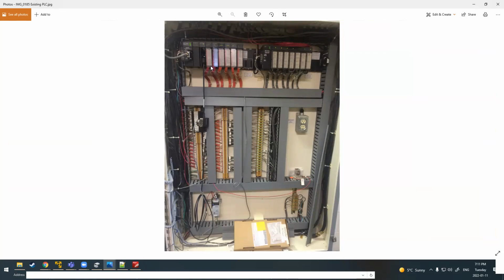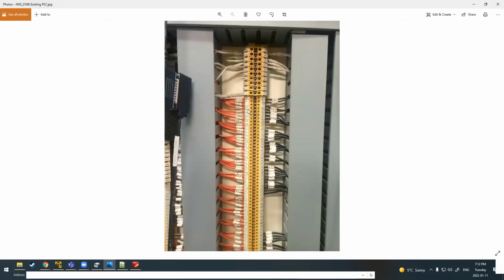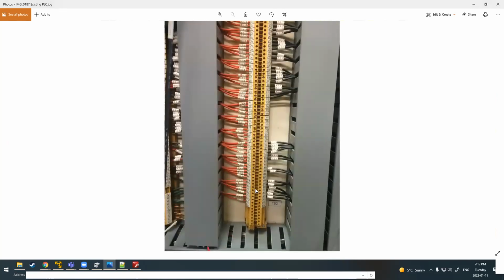All of your cards, sorry, I was answering Tatiana's question. All of these cards are wired down to terminal blocks. That is a big and very important component of any PLC panel. These terminal blocks, this is where your IO is then going to be wired up to your field devices. So you can see these wires, this is a good example of an old panel where these wires are labeled, and hopefully there are drawings that will tell everybody what these wires go to.